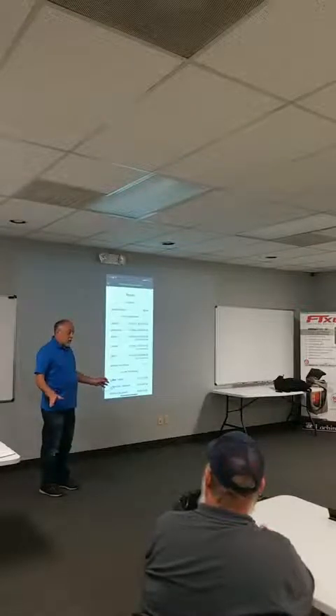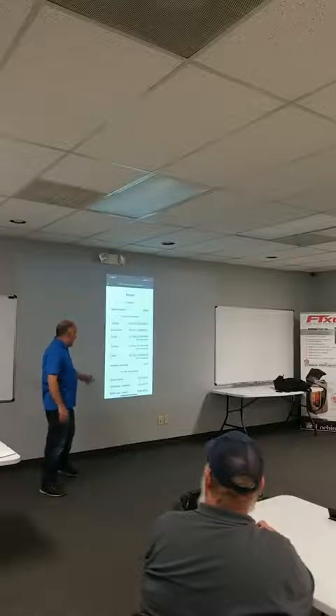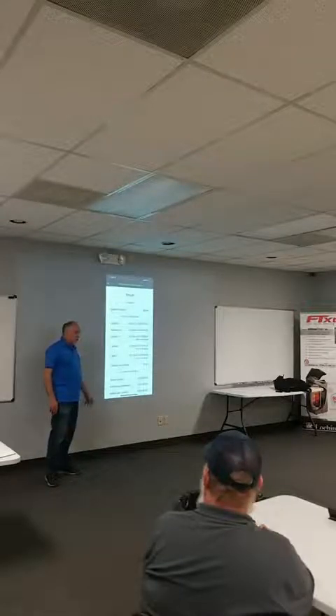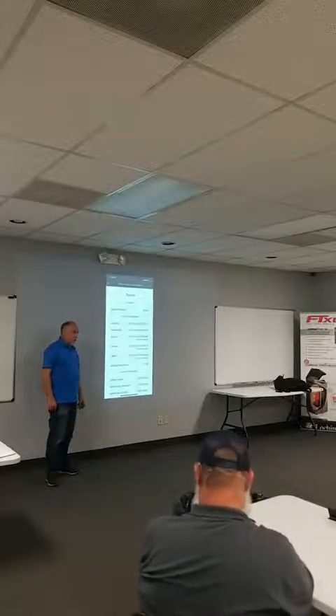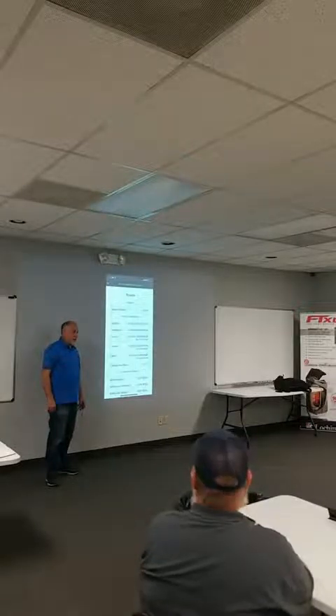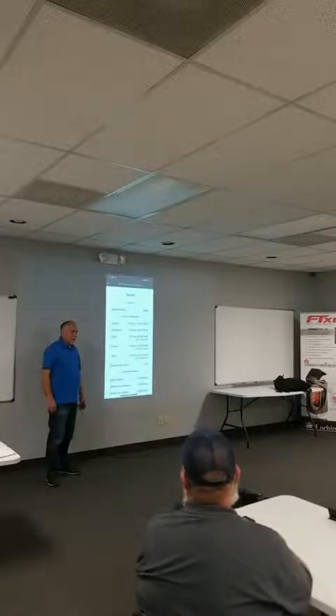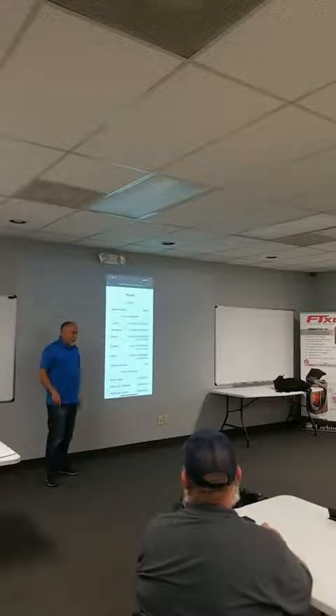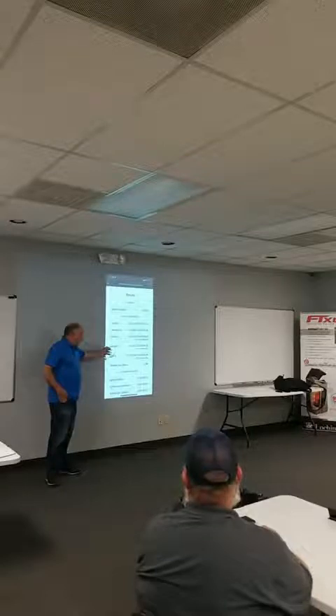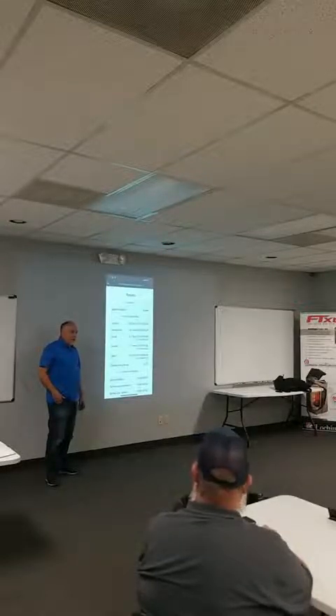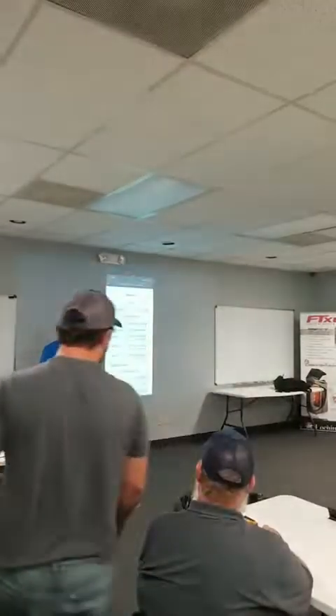Guess what? The humidity is pretty low in here. We don't need to remove much humidity. That capacity is going unused. That machine is fine. This is what's telling you that machine is running good. So you always want to look at your sensible capacity. It should be 95% or higher on a properly operating machine. We allow it to go down to 90% in MeasureQuick because we've just found industry-wide you can't always hit it, but I always shoot for 90% right here. It's running 99.7% of sensible capacity, which means that this machine's running perfect. Even though we have an overcharge on there, the machine's running okay.